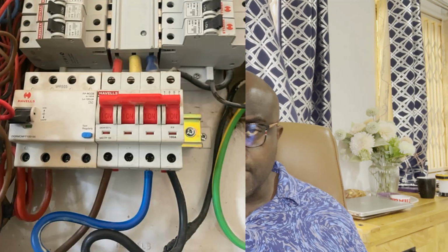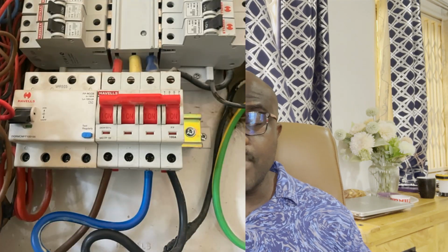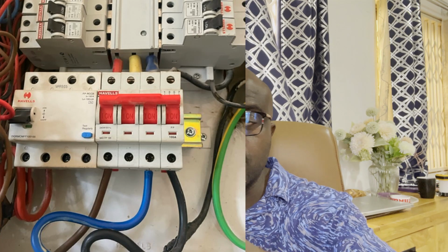Okay. Now, the distribution board incomer, the existing distribution board incomer, also for some reason only had 2 out of the 3 phases wired. Again, madness. I don't get it. Why do you have a 3-phase distribution board and only wire two of the phases? Something is wrong here. The system will be unbalanced. You need to balance the loads across all 3 phases.